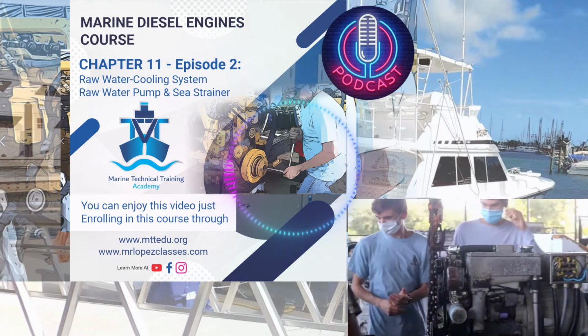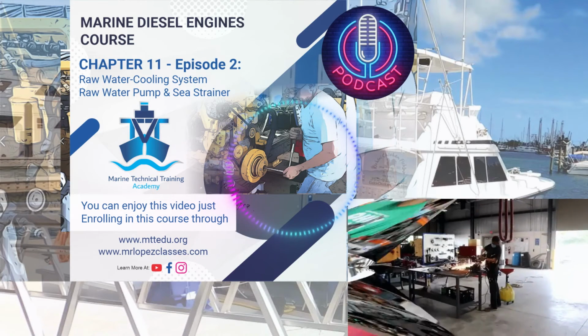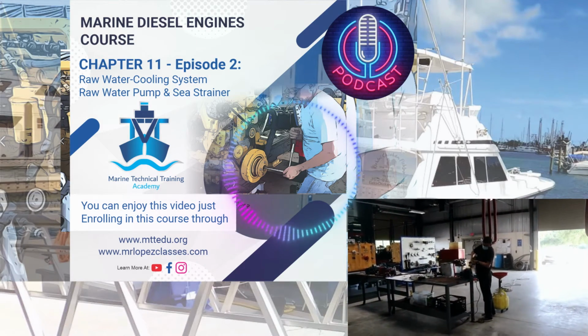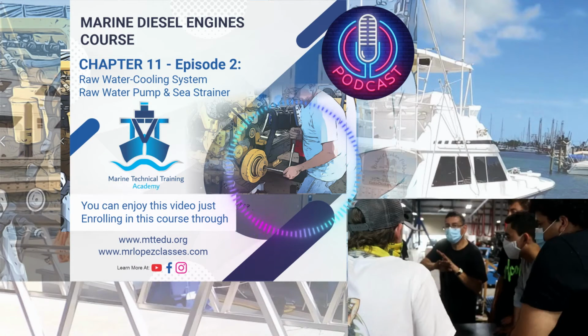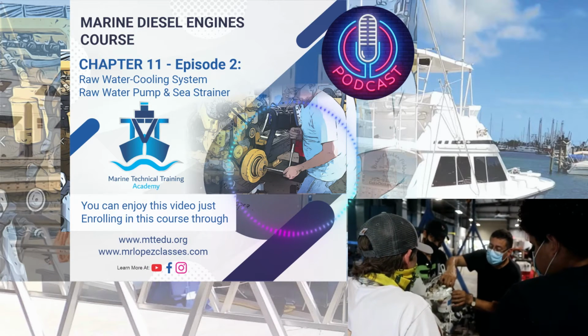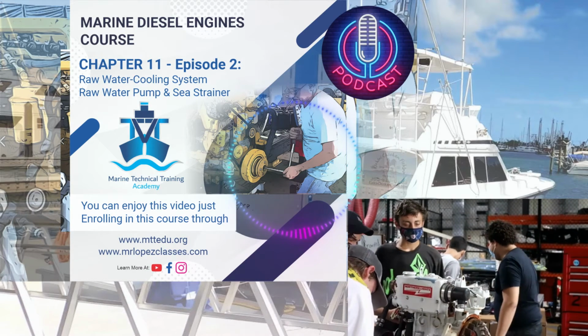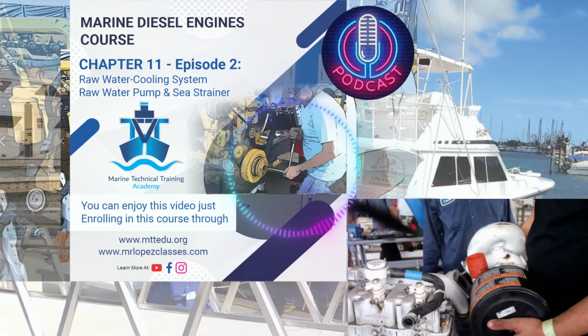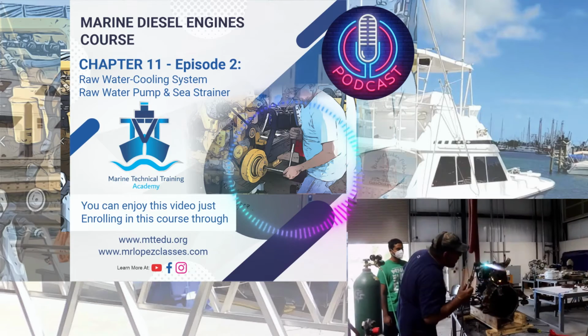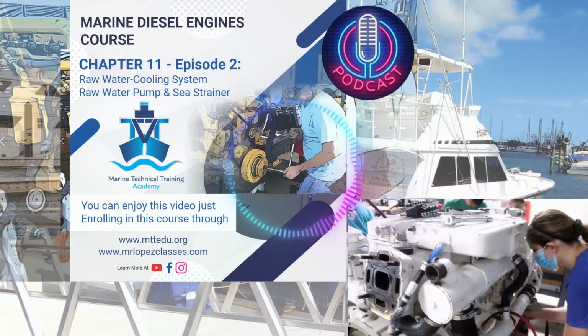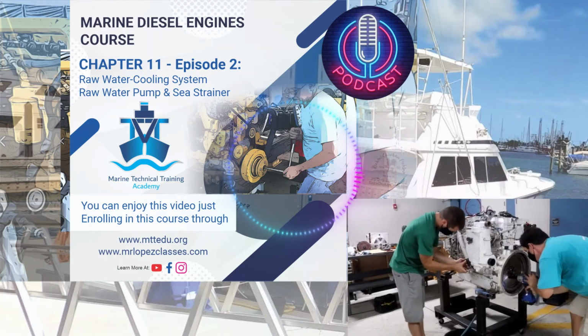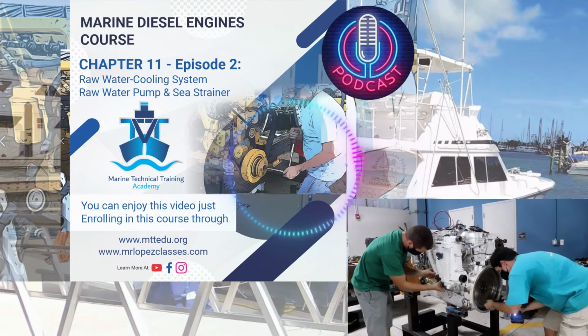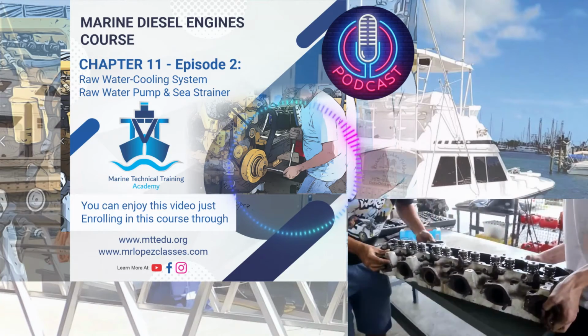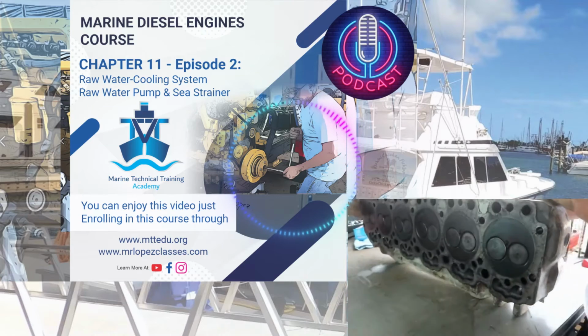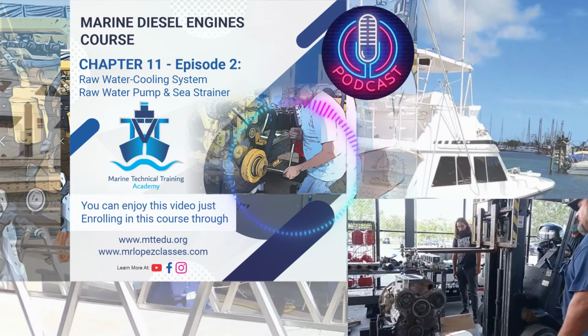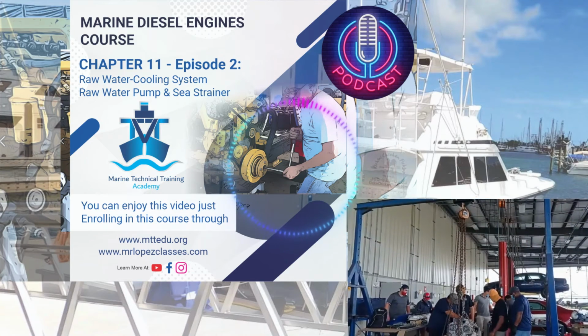Immediately after you start the engine, touch the plate of the pump. At the beginning, the plate is a little hot, but immediately the temperature decreases. This is an indication that the water is circulating in the pump, entering and passing through the pump. The procedure is: touch the plate, the temperature increases a little, but immediately goes down. If the temperature does not decrease, stop the engine and verify what happened with the impeller. Probably the half moon is not located over there, or the impeller was improperly installed. As soon as you start the engine, verify that you don't have leaks in the bottom of the pump, and that the pump is running properly.